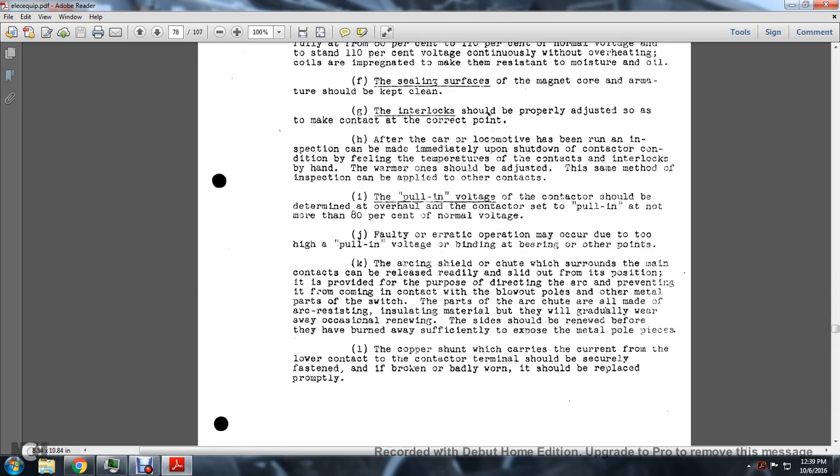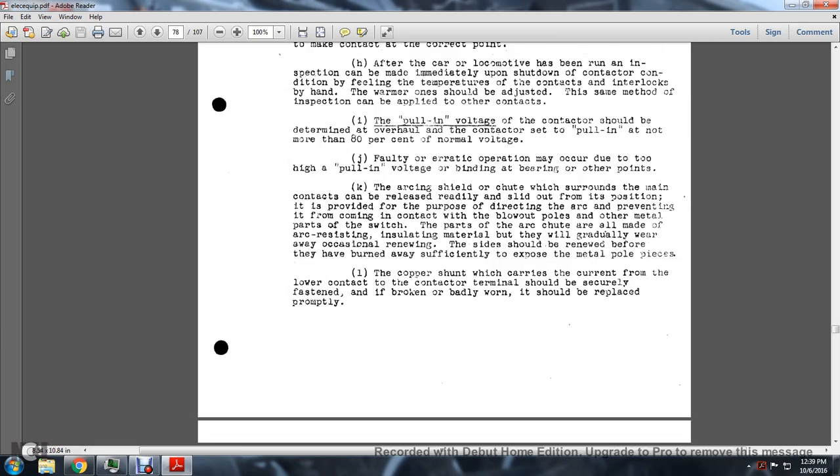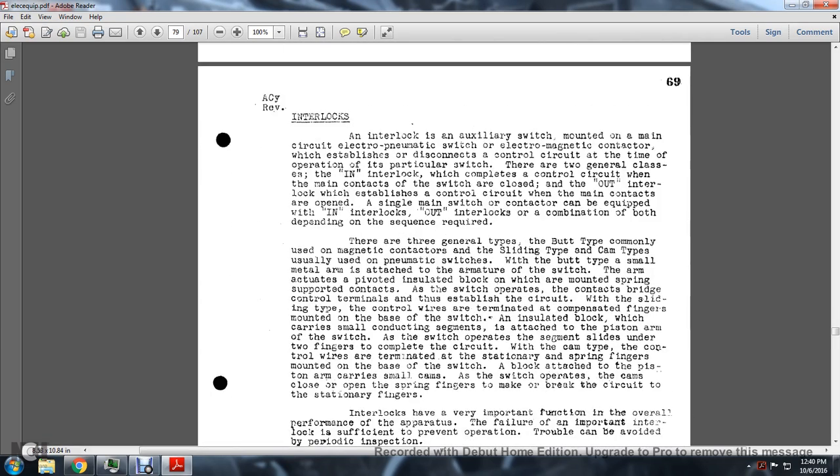The arc shield can be readily slid out from its position. It is provided for the purpose of directing the arc and preventing it from coming into contact with the blowout poles or other metal parts of the switch. The arc shield parts are made of arc-resisting insulating material that gradually wears away. The sides should be renewed before they are burned away sufficiently to expose the metal poles. The flexible copper shunt that carries current to the lower contact terminal should be securely fastened; if broken or badly worn, it should be replaced promptly.